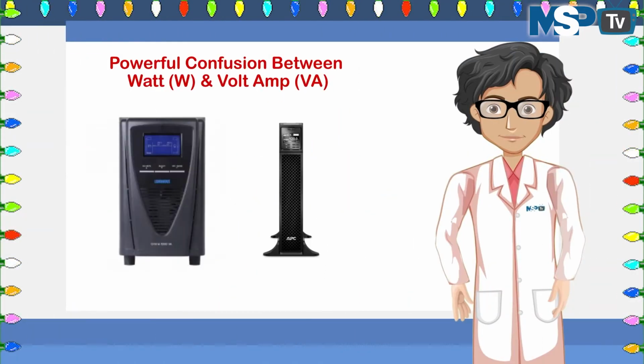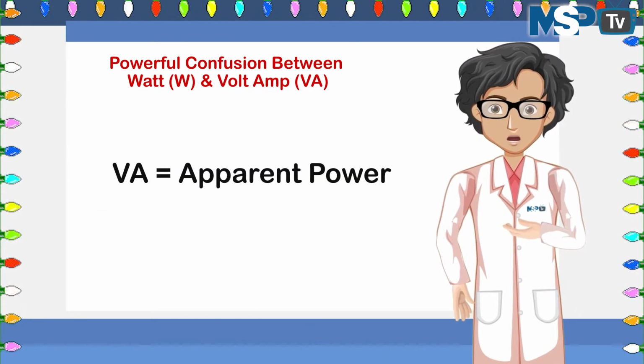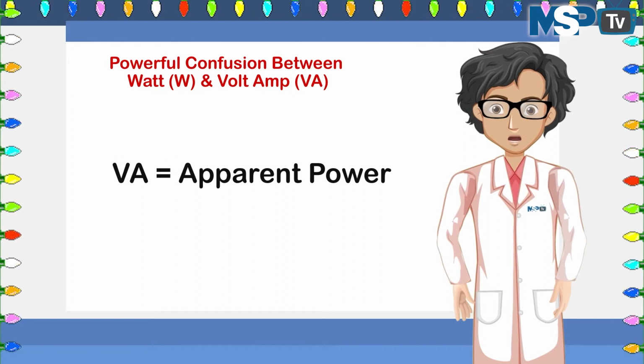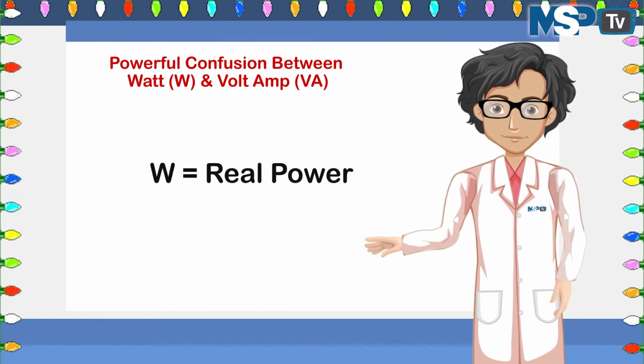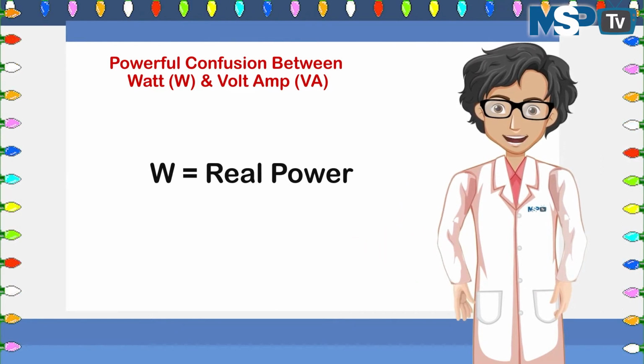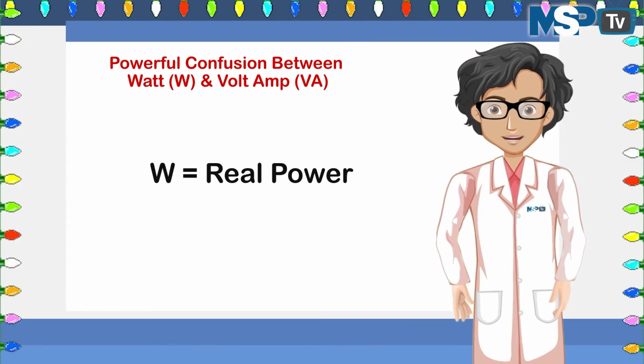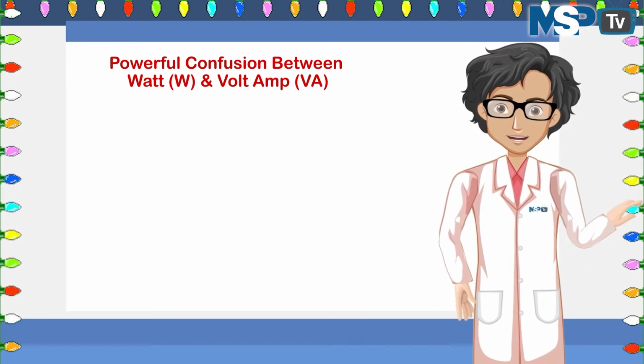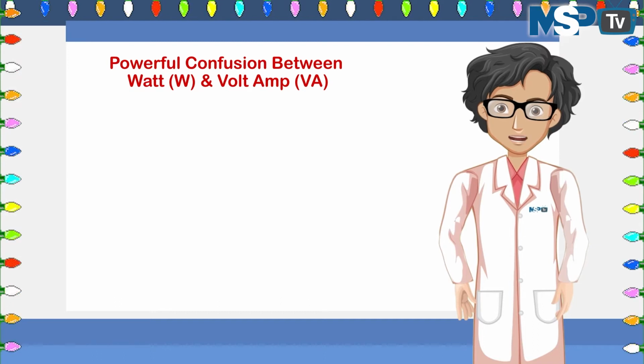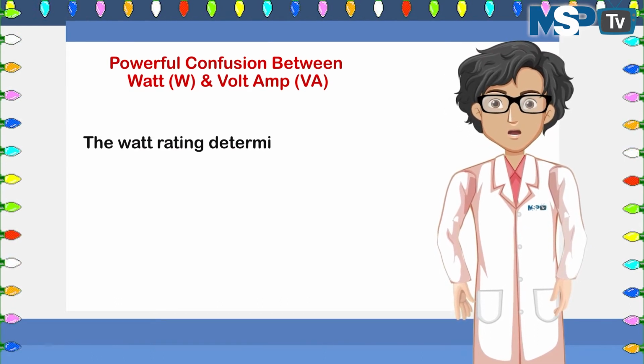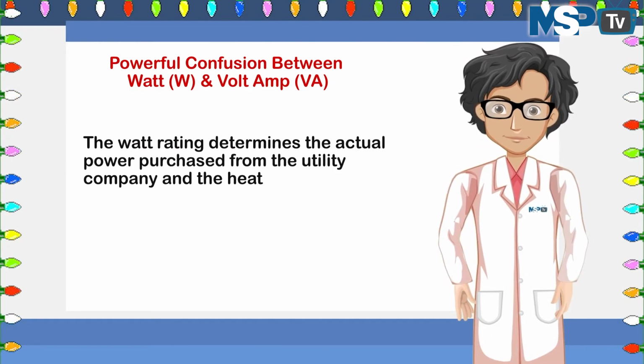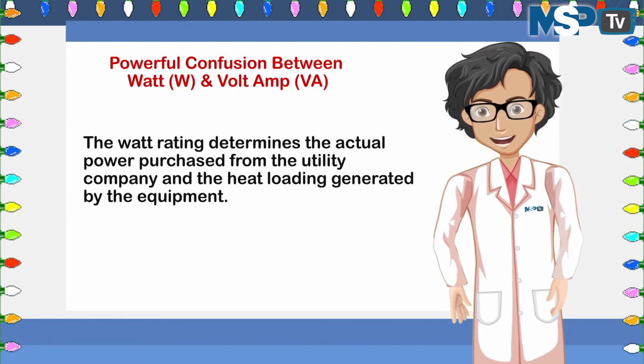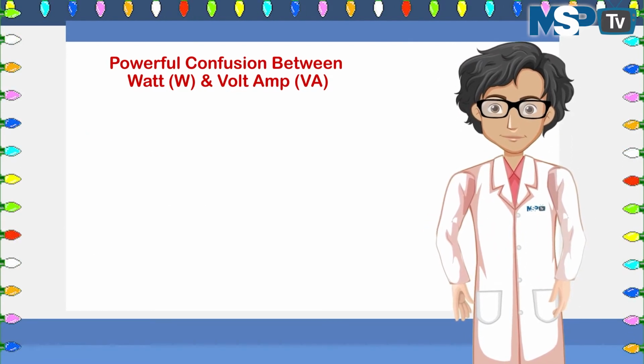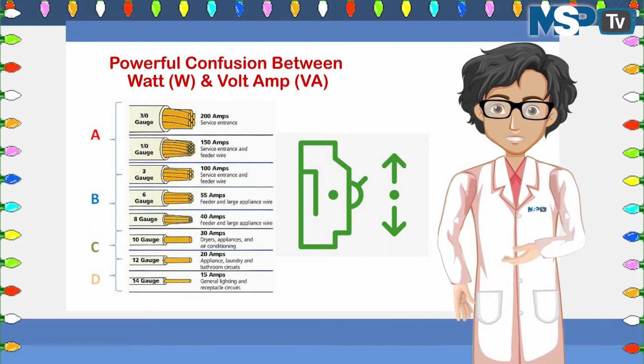For systems like UPS and inverters, VA rating is apparent power, or the capacity in which it is available in the market, and watts is the real power which equipment can actually deliver to the load. Both watt and VA rating have a use and purpose. The watt rating determines the actual power purchased from the utility company and the heat loading generated by the equipment. The VA rating is used for the sizing, wiring and circuit breakers.